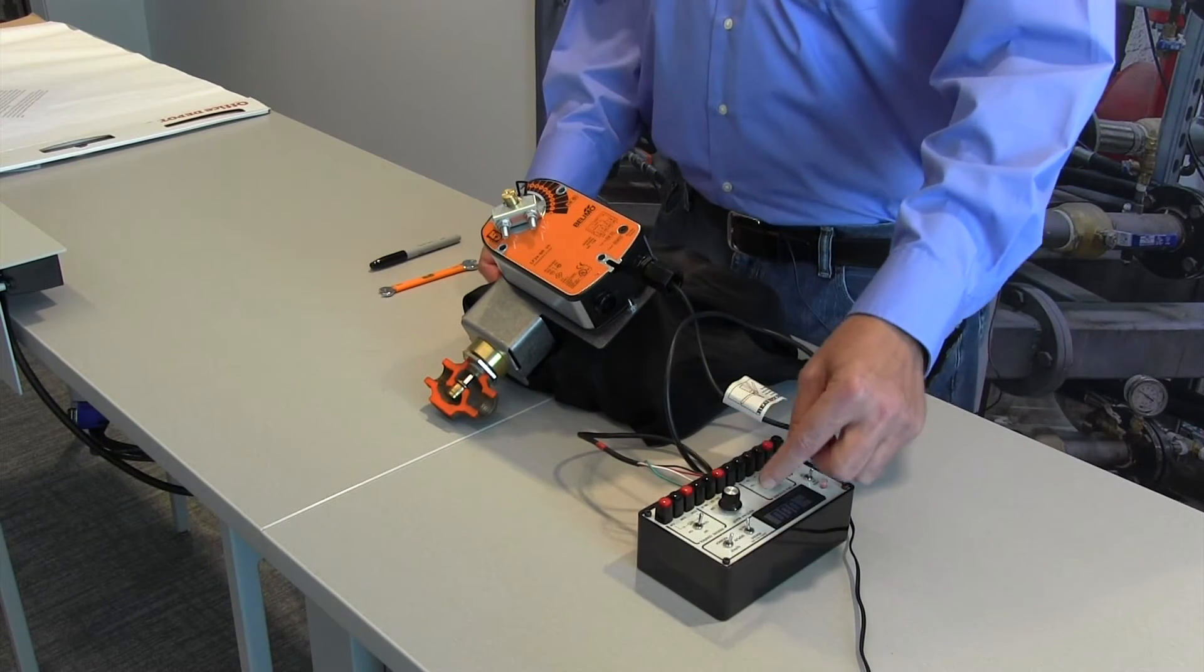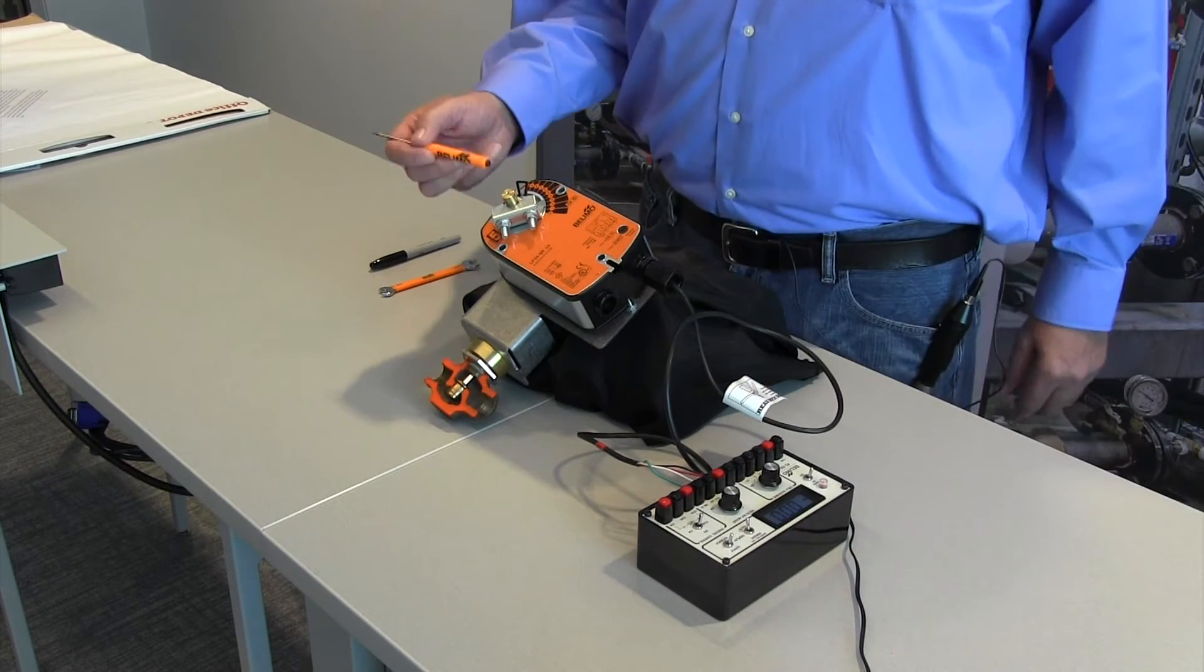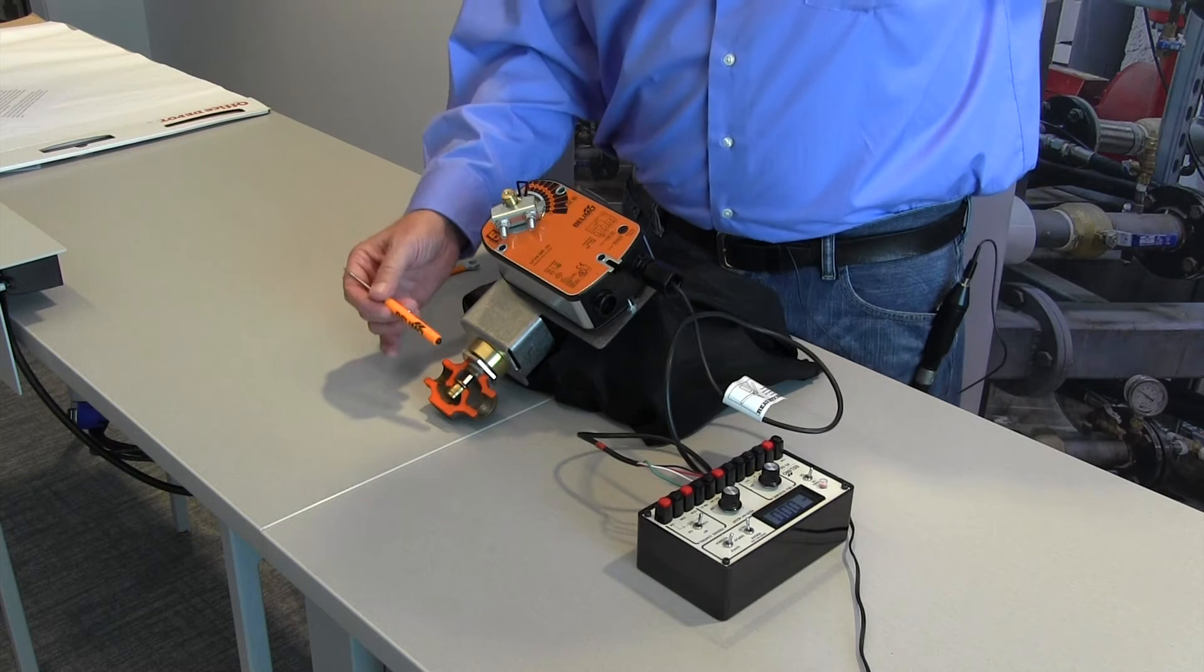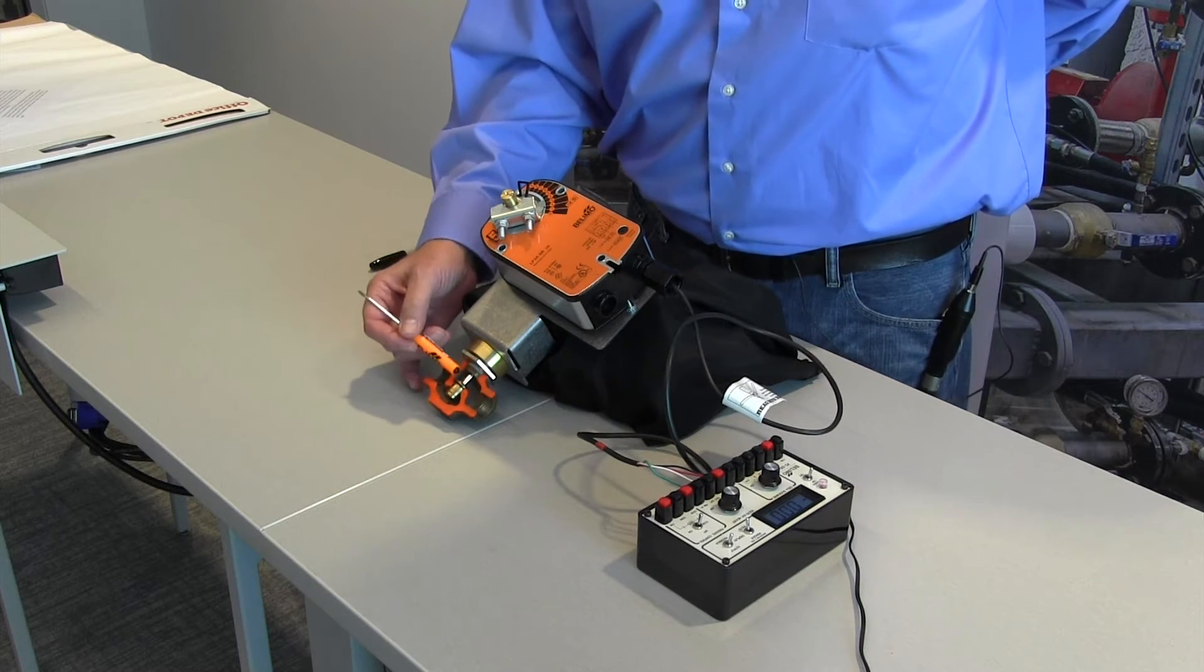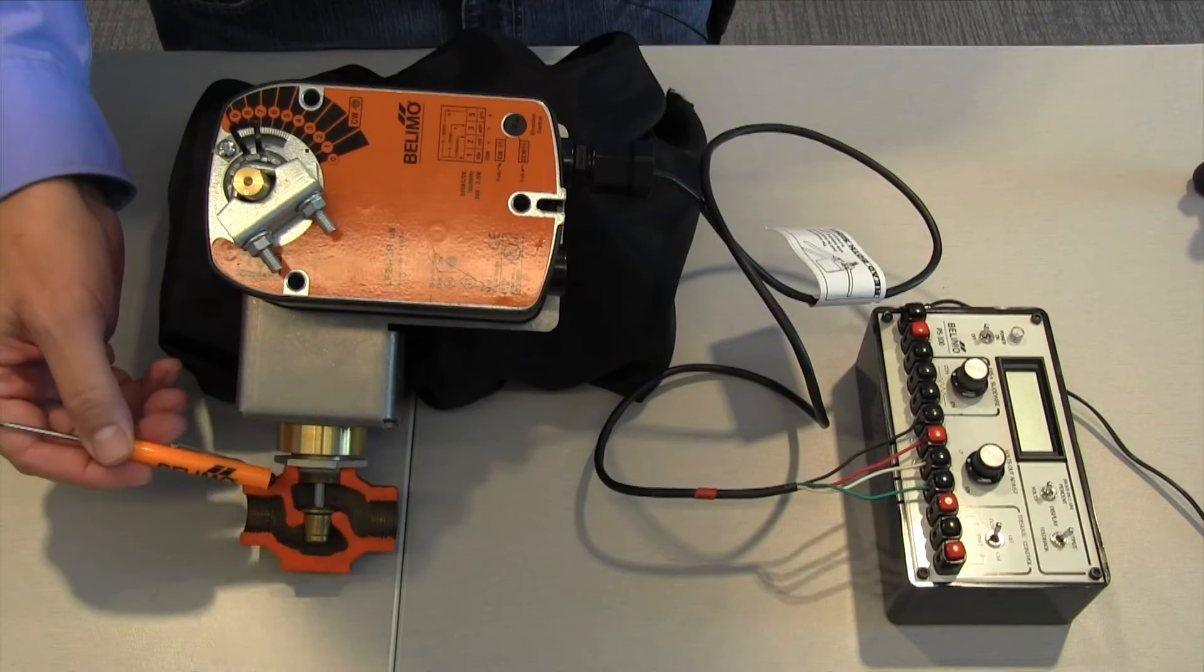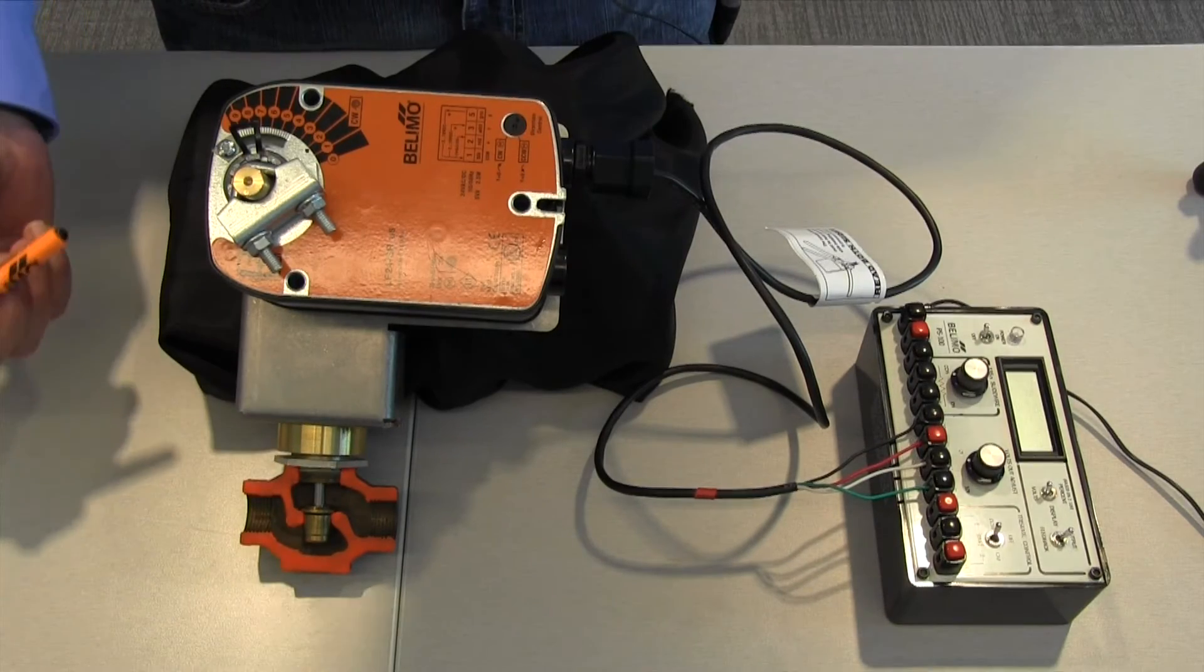I'm going to go to zero on my signal control. The actuator is going to begin to close and now what's happening is the actuator is putting steady constant pressure on the valve seat. You're getting much better close off.